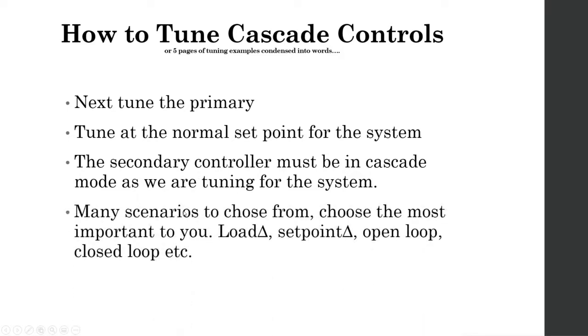There are many, many scenarios to choose from, so choose the most important ones to you. Make sure you tune it for, for example, are you more concerned about the effects of load changes? Are you more concerned about the effects of set point changes? Do you have to do an open loop test to get your baseline values? Can you do a closed loop test to get your baseline values? If you're in an operating plant, you're probably not going to be able to do an open loop test. You might have to do a closed loop test. So there's a bunch of different things that you have to consider.